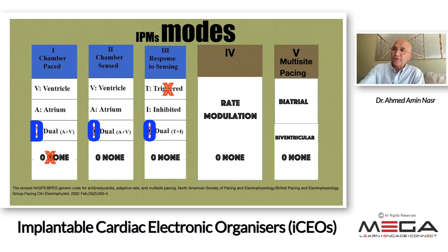A simpler approach to understanding iCEOs has nothing to do with exams, but rather improves our understanding. It is intuitive to consider chamber sensing first, second planning response, then chamber paced, and at last, the off mode. So the primary step is what is sensed? Is it atrium, A, ventricle, V, atrioventricular, AV, or atriobiventricular, ABV, or none at all, which means it is becoming an asynchronous pacemaker. The plan of response is either I, inhibited, or IT, inhibited and triggered, or R, modulating, or asynchronous mode, an asynchronous response, which is actually planned by the computer of the pacemaker.